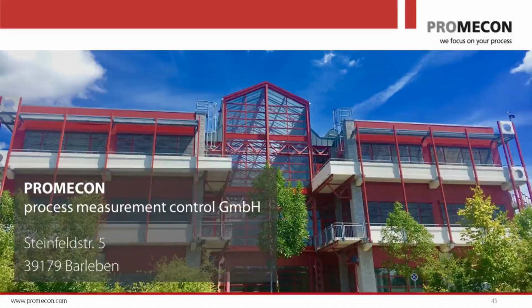There is no regular maintenance on these sensors, but what we, of course, would definitely recommend is that you look at the sensors, you look at the system at every overhaul. So you don't have to go to the boiler house every other day or every other week, check the sensors, blow out lines, all that's gone, that's the past. So I would say maintenance is another very big advantage of this measurement system. Only regular care about your sensors when you have larger overhauls or maintenance cycles in your plant. So that's all, and it's usually a visual inspection. There's nothing to test or recalibrate because it's a clock. This airflow measurement is basically a digital clock. That's all it is.